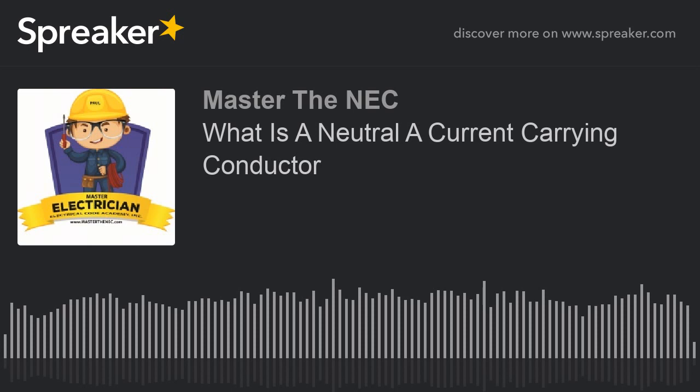Well, if that's the case, then each one of them does get qualified as a circuit, even though it's called a multi-wire branch circuit. Each one of them qualifies as an individual branch circuit. They're just simply sharing a neutral. And so when it goes out, it's the same concept. If I have 10 amps on the red, and I have 5 amps on the black, then as we know by now, the unbalanced current is going to be 5 amps traveling back on the neutral. And so in that scenario, I do not have to count that neutral conductor as a current carrying conductor. Okay? So that's what 5A is telling us.